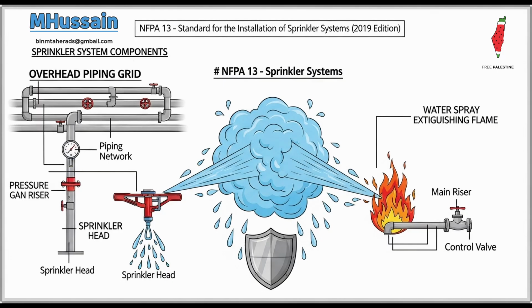It often forces a move from simple control mode density area systems up to early suppression fast response, or ESFR, sprinklers. What's interesting, though, is that the protection criteria designed for Group A plastics can actually be used as a sort of design default for the lower hazard classes, too. Yes, that's right.